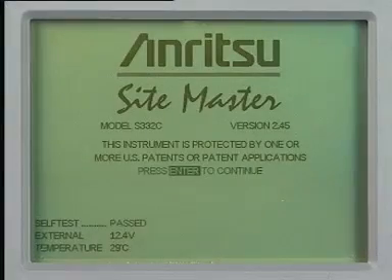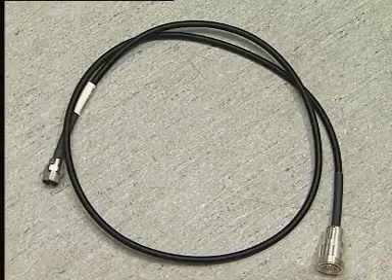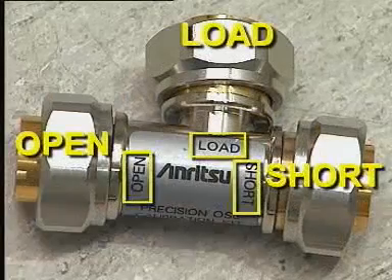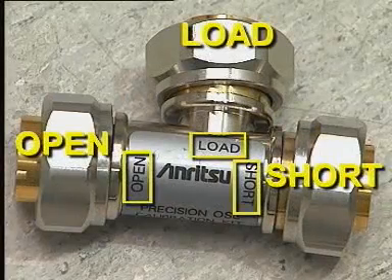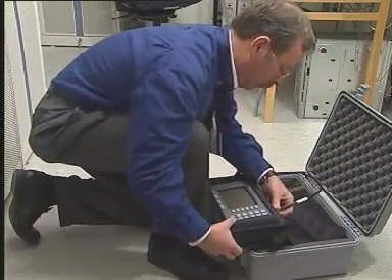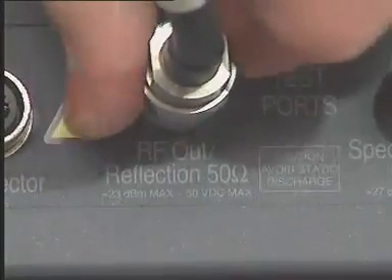The Site Master package contains a phase-stable extension cable and a calibrated terminator. Connect the extension cable to the RF-out reflection socket. The calibration will take into account the properties of the cable so accurate measurements can be made.